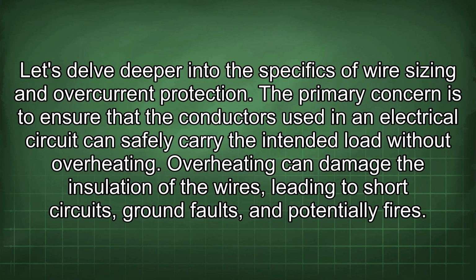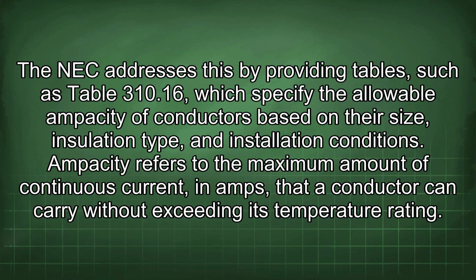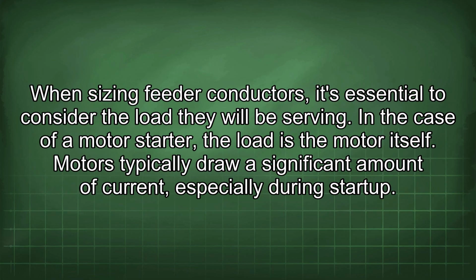The primary concern is to ensure that the conductors used in an electrical circuit can safely carry the intended load without overheating. Overheating can damage the insulation of the wires, leading to short circuits, ground faults, and potentially fires. The NEC addresses this by providing tables, such as Table 310.16, which specify the allowable ampacity of conductors based on their size, insulation type, and installation conditions. Ampacity refers to the maximum amount of continuous current in amps that a conductor can carry without exceeding its temperature rating. When sizing feeder conductors, it's essential to consider the load they will be serving.